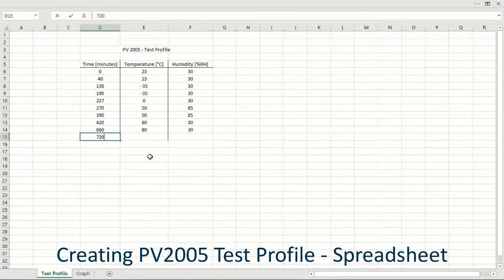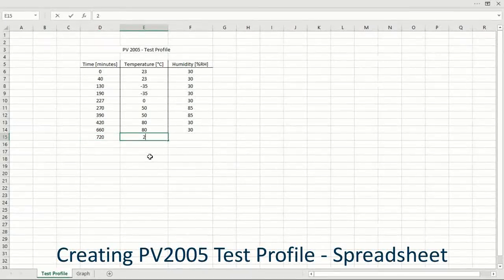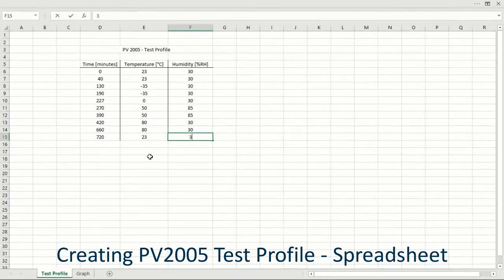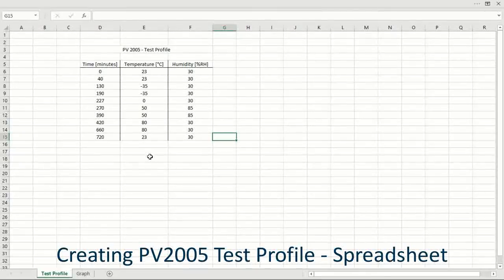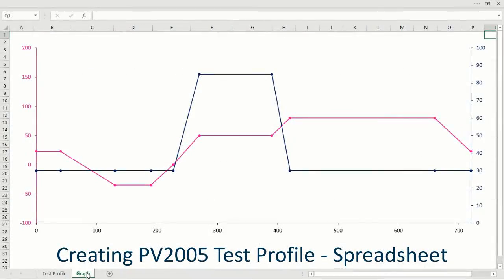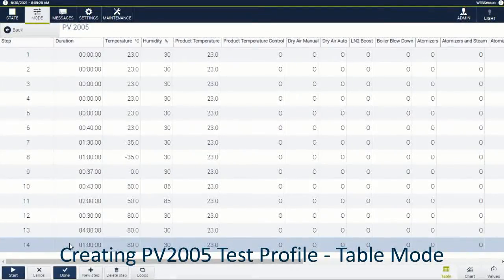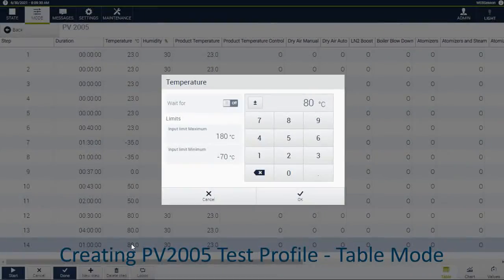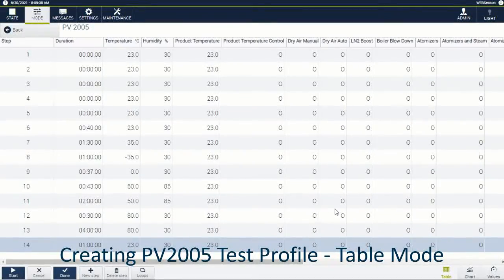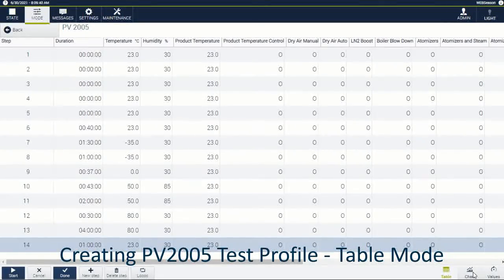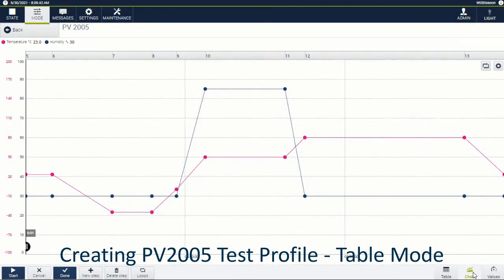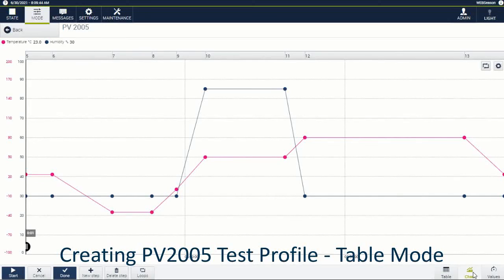Some industry-standard tests are presented in spreadsheet form, and they have to be copied to make a new test profile. With WebSeason's table mode, all the steps, conditions and set points can be easily transitioned to a test profile by viewing all the information at a glance. Programming temperature and humidity set points step-by-step is no longer required, giving you complete control.